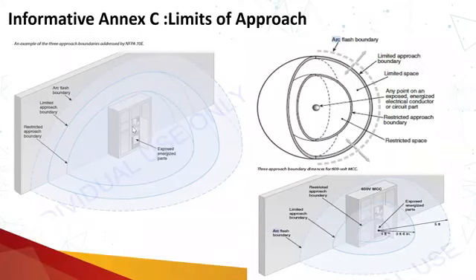If this panel door is closed, these boundaries do not exist. If this panel door is open and I'm interacting with that particular equipment, then these boundaries exist: the arc flash boundary, limited approach boundary, and the restricted approach boundary. If this panel door is closed, but I am performing some switching operations, interacting with this particular equipment locally or remotely, then the boundaries will exist.